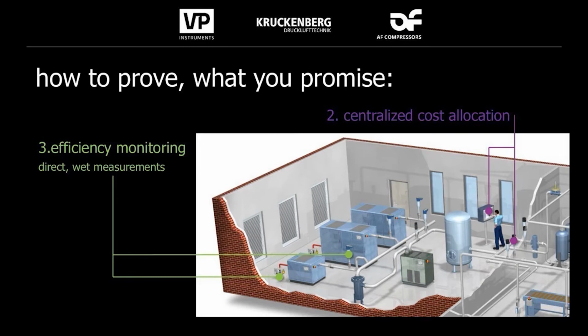But at this customer, we had the problem. We had 3 old air compressor stations distributed over the whole facility. And our task was to create a new centralized room for the compressed air supply side. And we also had to find a good location for it, so that the pipeline and the supply could be diversified in the production without big losses.